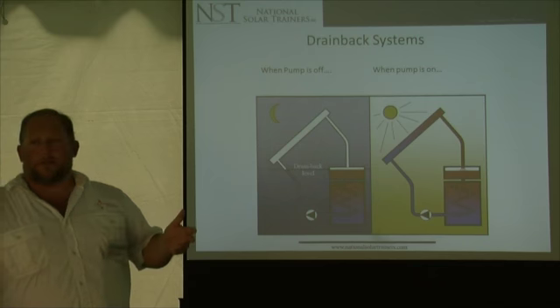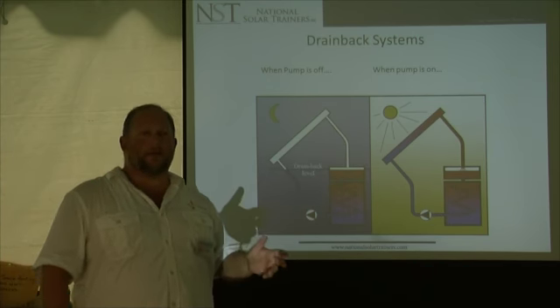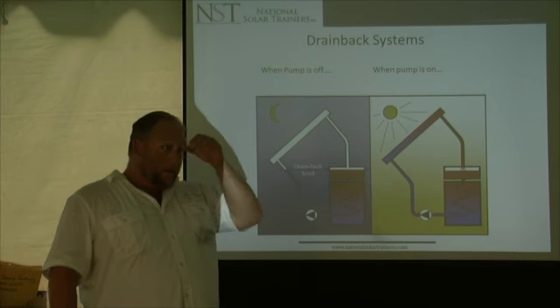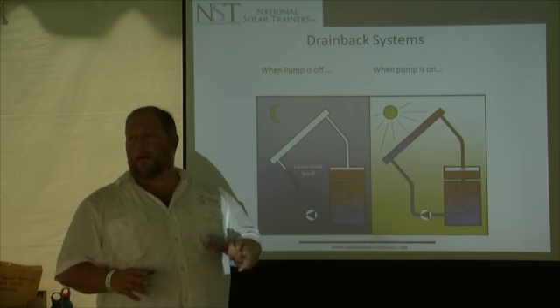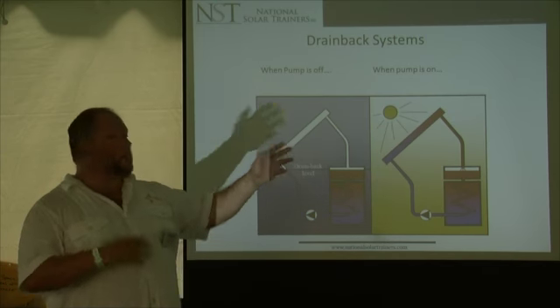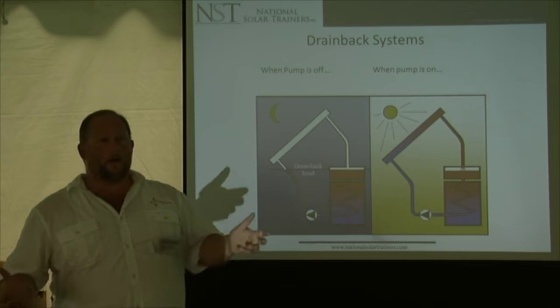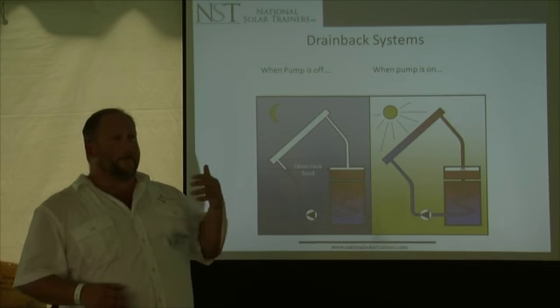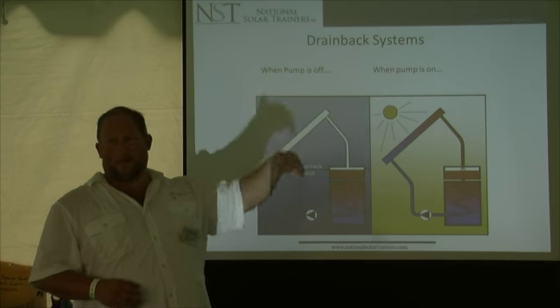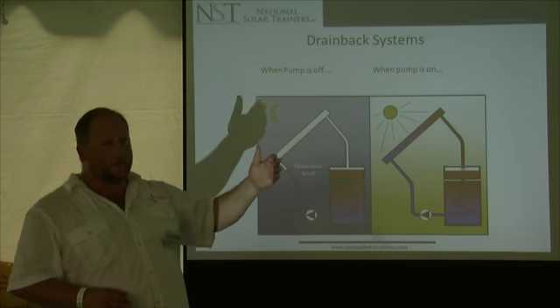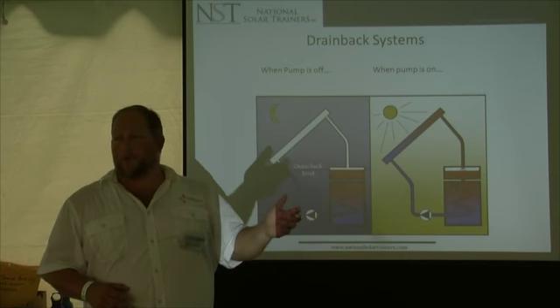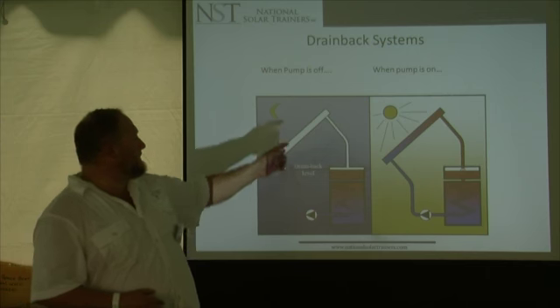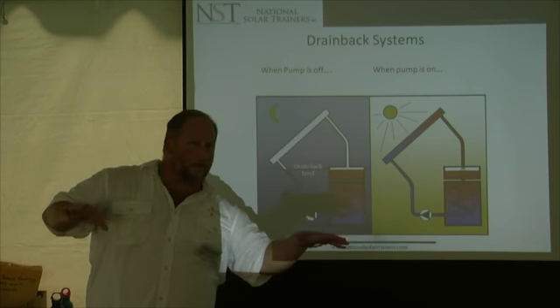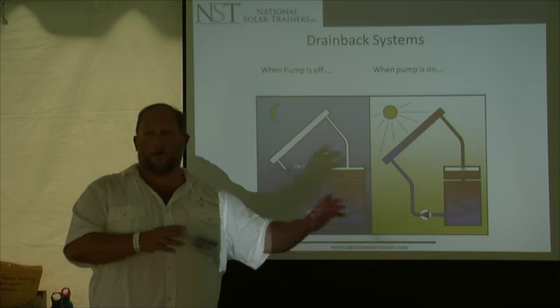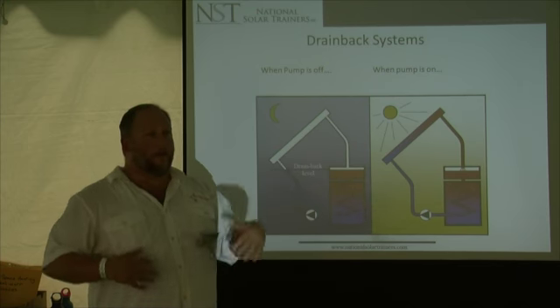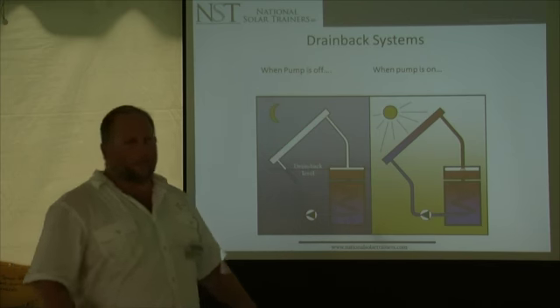There's also a system called Drainback. A Drainback system doesn't need glycol — it drains back at night into a reservoir so the water doesn't freeze. This allows us to use water circulating through the collector. It's still a closed loop, but it uses water instead of propylene glycol. The challenge is the collectors have to be tilted on the roof so they slope downward, and all the piping has to drain properly, or it will freeze.